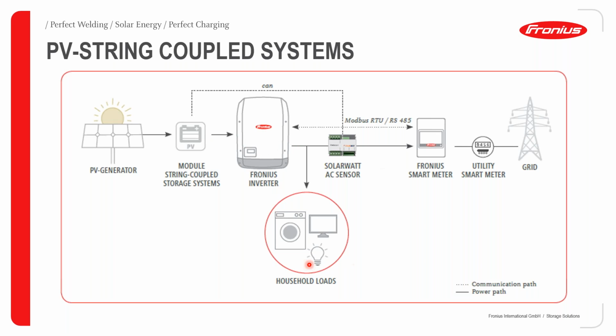So let's say the Fronius inverter detects that the loads maybe require 3 kilowatts of power or 4 kilowatts of power. It will then send a signal to our module string coupled storage system and tell it to please send the inverter 3 kilowatts of DC power so that it can convert it to AC. Okay, and basically in the system we also have the solar watt AC sensor, which also communicates directly with the module based storage system. And this in turn will also communicate with our Fronius smart meter, which will again measure all the energy flows in the system. And in between the Fronius smart meter and the Fronius inverter will then have the AC loads.